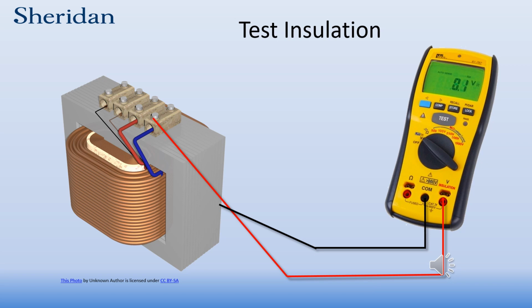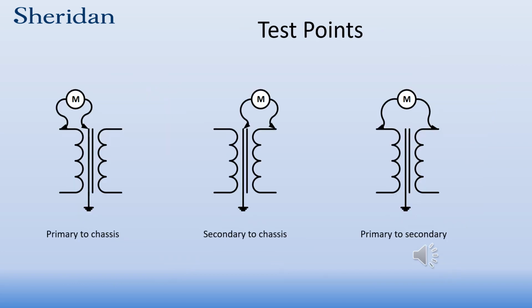It is recommended that you test every terminal to make sure that there is no weak insulation between those windings and the chassis of the transformer. You must test everything in a transformer, and what we're showing in this presentation is actually very simplistic. But what you do test is between primary to the chassis or ground, from secondary to the chassis or ground, and between the two windings, which would be from primary to secondary. This way you can ensure that the insulation to the chassis, or between the conductors of opposing windings, is in fact good.